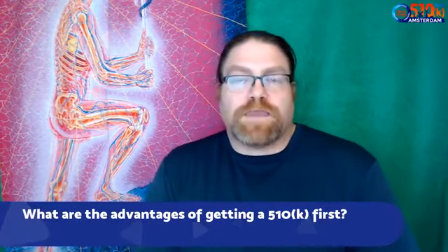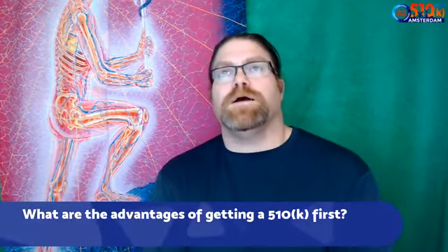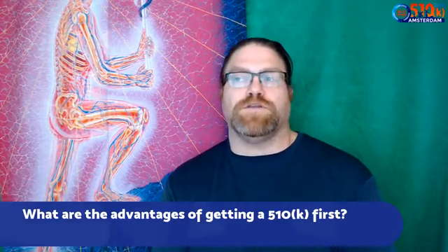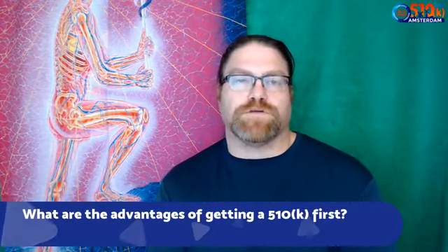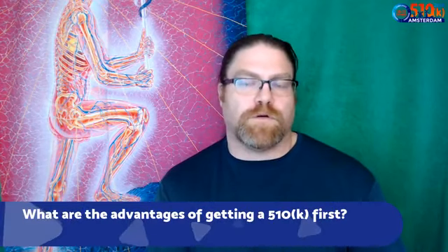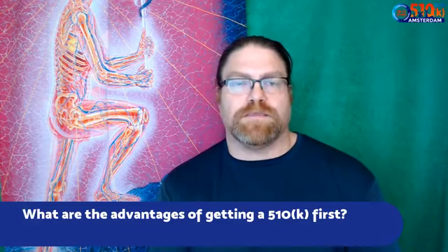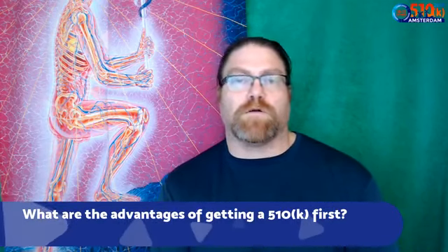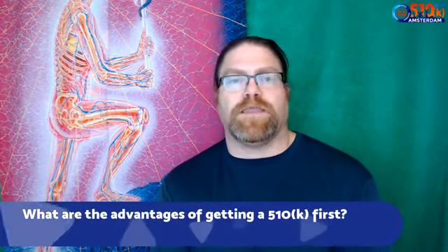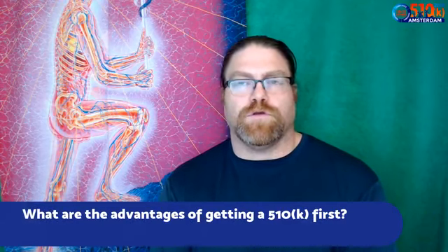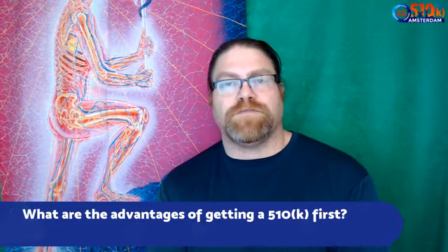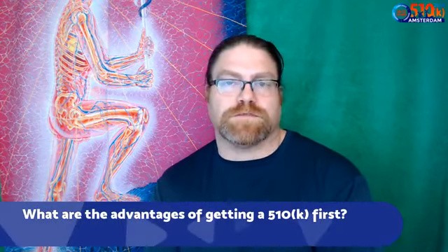What are the advantages of getting a 510K first, other than, of course, the one I just gave you? Well, one of the reasons is if you are a small company, you're a startup company, and you don't have a lot of money, you're not required to get ISO certified to do business in the US. So in Europe, you typically are going through the ISO certification process, or you have to be audited by a notified body to the MDR or the MDD currently. And that costs a lot of money. They charge a hefty fee. Whereas in the US, you're supposed to be compliant with the 21 CFR 820, the QSR, but the FDA doesn't actually come to do an inspection, and they don't charge for those inspections.